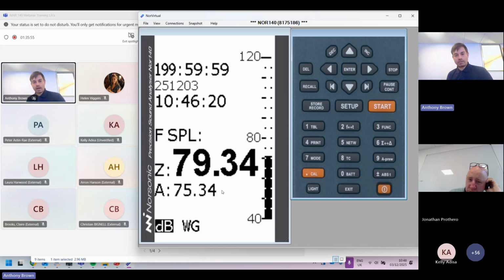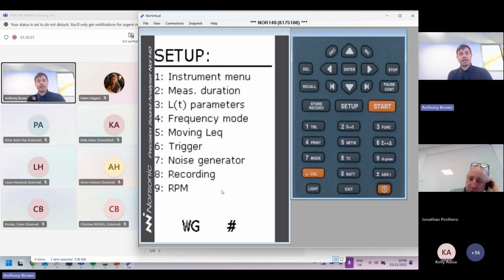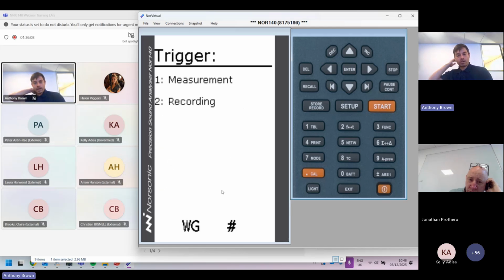We're going to go into setup, and the meter's waiting on a trigger. So we need to go to the trigger menu, number 6. It's waiting on a specific trigger called measurement, which is in number 1. Earlier we changed the settings for recording, number 2, but we didn't change the setting for number 1, measurement. I did that on purpose because often it's already set to the right setting and I don't want to confuse things. But sometimes someone before you has changed this measurement number setting, which they shouldn't have.